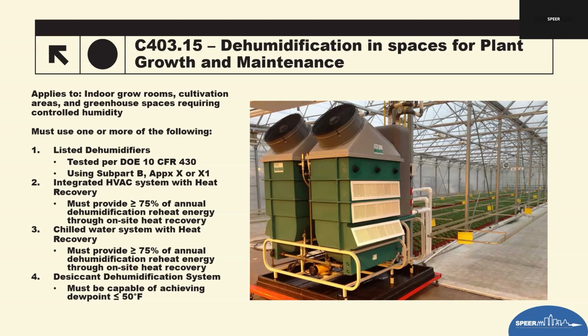So there's several options. First one is listed dehumidifiers. The first compliance path is to use these packaged dehumidifiers that are tested and rated to a DOE standard 10. These standardized test procedures are designed basically to ensure predictability, performance, and verified efficiency. And then number two, integrated HVAC with heat recovery. So another option is to design the integrated system to also have a heat recovery system capable of providing at least 75% of the annual reheating energy required for dehumidification. This approach captures wasted heat. That's what we just said a second ago, and the primary reason they're there is you're capturing wasted heat.